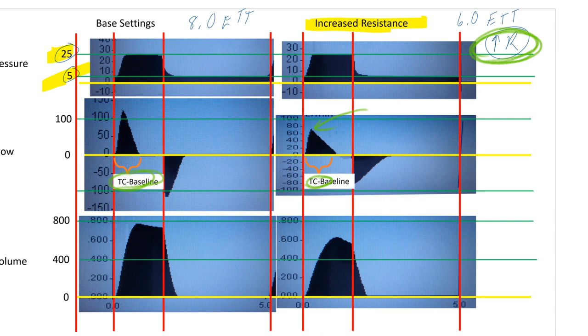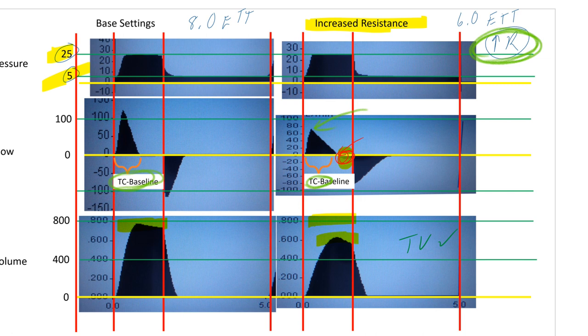We can see the increase in time constant on the ventilator. Because we still have an inspiratory pause, there should be equilibrium between mouth and lung pressures, and compliance was unchanged. However, tidal volumes were slightly less, which may be due to the inspiratory flows being so reduced by the slope that complete volume delivery didn't occur despite the apparent pause. Flow rates are decreased and time constant has been increased, which is consistent with the increased resistance.